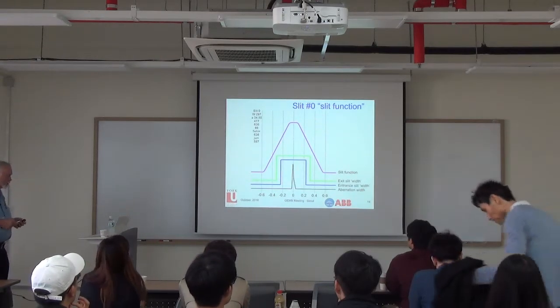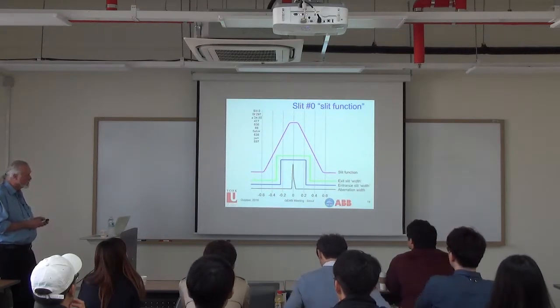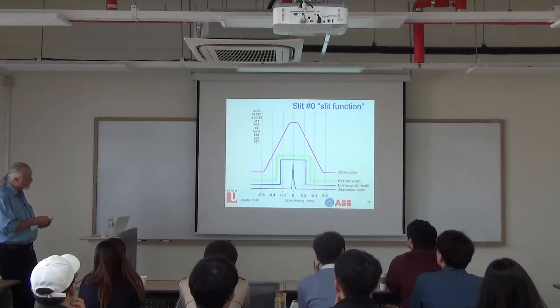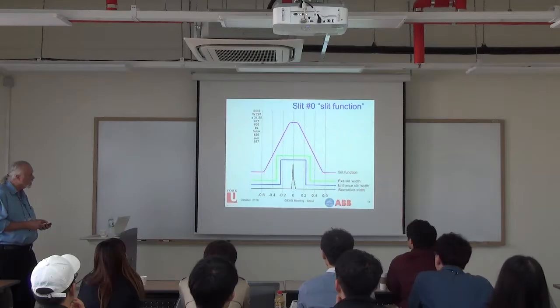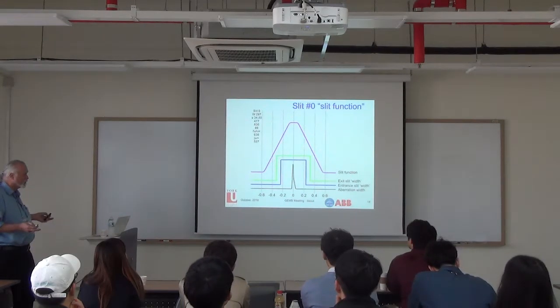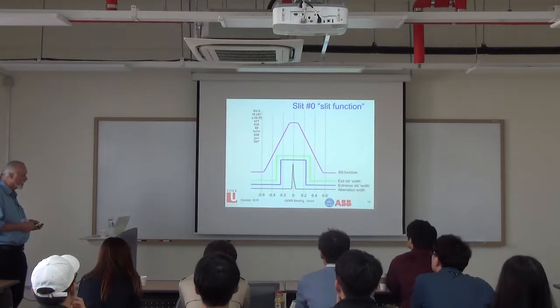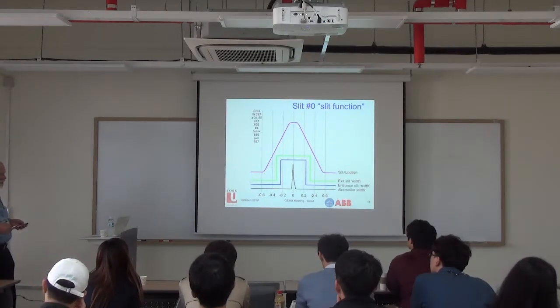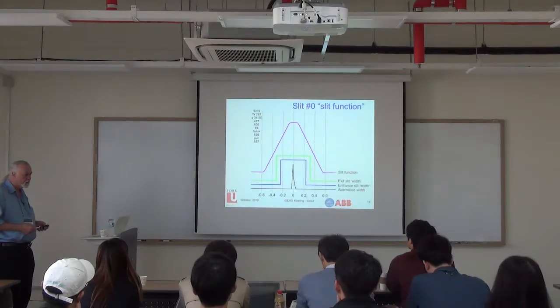The inclusion of the correction lens means the optical performance is very good, so the slit function can be approximated as a trapezoid to high accuracy. This means we can do simple lab tests to determine the slopes and the width of the flat top, and accurately calculate the cross-section applying to each wavelength—giving an accurate estimate of the instrument's response to ozone.